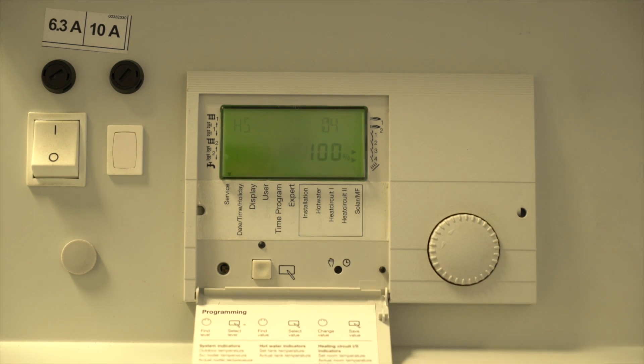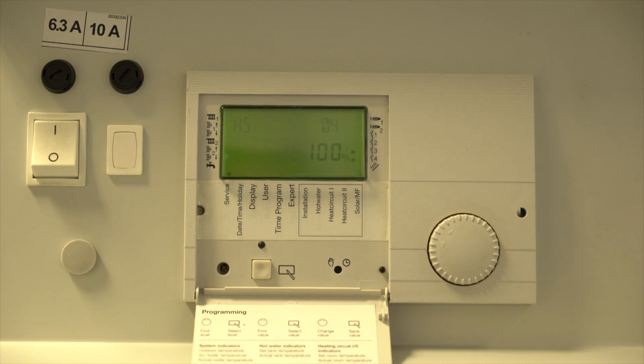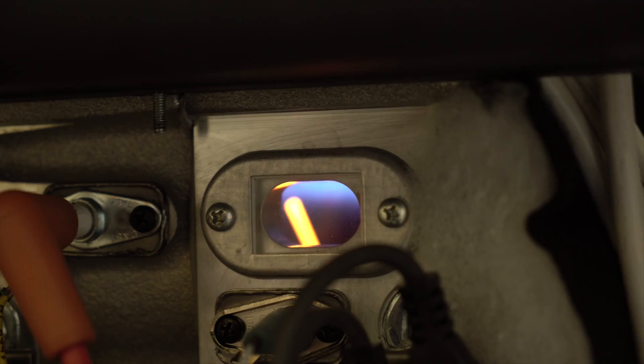Check combustion results at 100%. Once satisfied, reduce output to 0% and repeat procedure on each module.